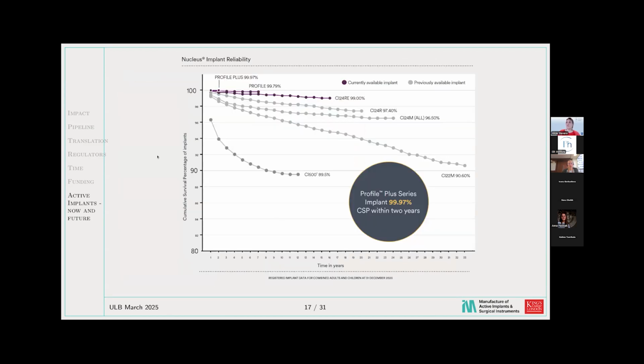In terms of reliability, as I've been mentioning a lot, this is publicly available data from Cochlear, one of the largest manufacturers of cochlear implants. You can see over time, we have 33 years of data for the older generation of devices. After 33 years, the old generation had 90% reliability. That means these devices were first put on the market in the 1980s, so technology made in the 1970s was already capable of achieving 90% reliability after 33 years in the body.